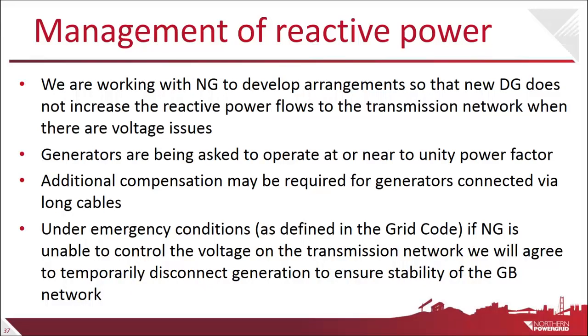We've also discussed a potential scenario where if all of the distributed generation is operating, then the amount of generation on the transmission network directly connected that National Grid can control, to balance the network and control voltage, can become too small. So under some emergency conditions there can be a requirement to temporarily disconnect generation on the distribution networks to maintain the stability of the whole GB network.